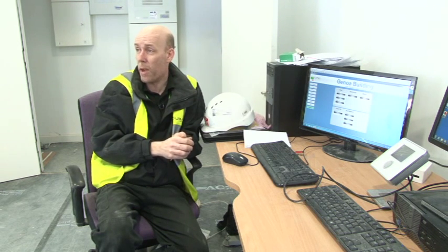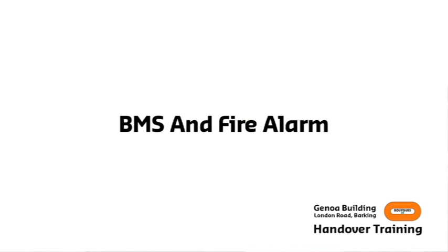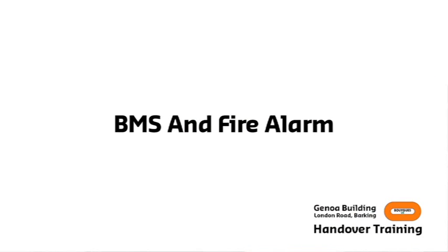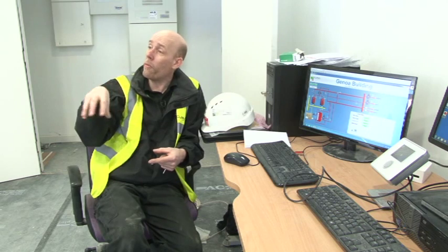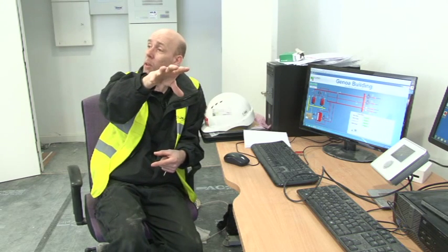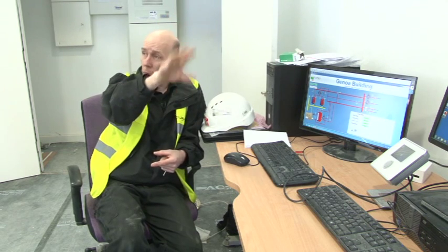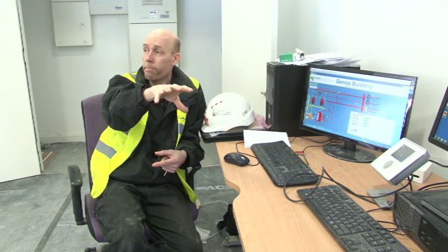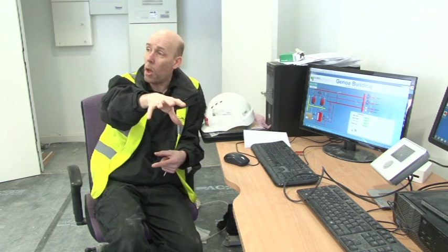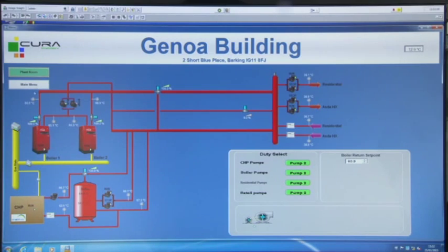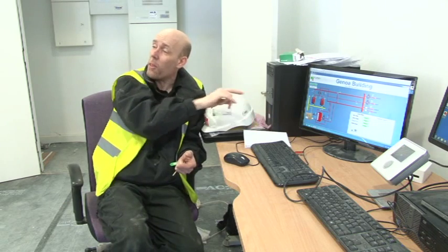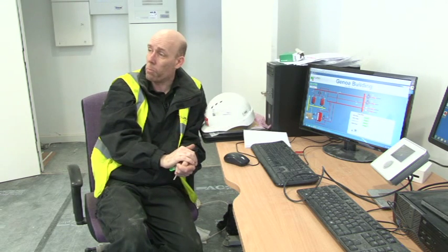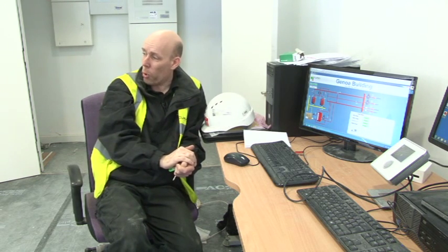It's a legally bound meter. When the fire alarm goes off, because the fire alarm is connected to our panel as well, when the fire alarm trips, it stops all the plant in the plant room automatically. As soon as the fire alarm goes off, all of the plant stops, shuts down. When it resets, the plant will restart from whatever it was previously doing. The alarm will come on here if that is unreset, and when you reset that, this alarm will then clear to say there is no longer a fire alarm in the plant room. And then it will switch all the plant back on.